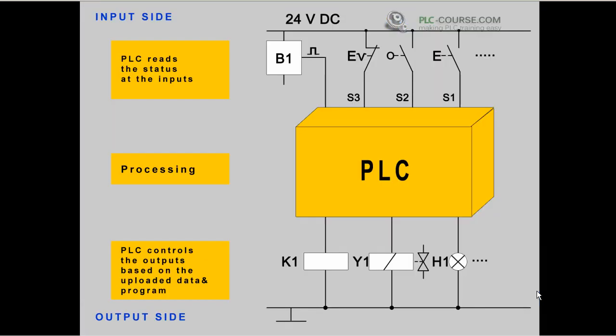Now we will take a look at the way a PLC works. PLC works in programming cycles. It means that it first reads the status at the inputs, then goes to processing, and then based on the program that is in its internal memory and based on the data that it has uploaded at the beginning of the cycle, it controls the outputs and executes any commands.